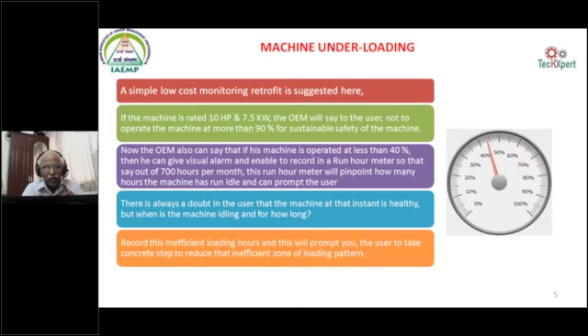This is one of the areas where the energy efficiency of the given motor can be sustained, if you have a right type of loading, say between 60 to 80%. If you are operating the motor at less than 40%, what can be done? If you are operating the motor above 90%, what can be done? Whenever you go and stand in front of the machine, at that time you will find, oh sir, my 10 HP motor is running at 6 kilowatt, it is excellent. But when you have moved away from the machine, the machine may go for idling and it can run at 4 kilowatt. So things can happen everywhere.